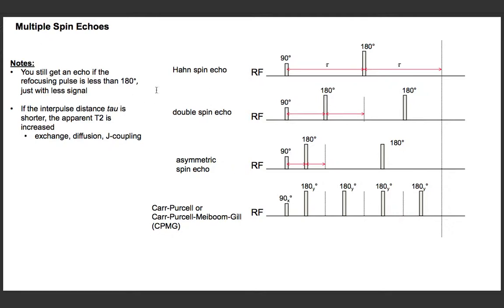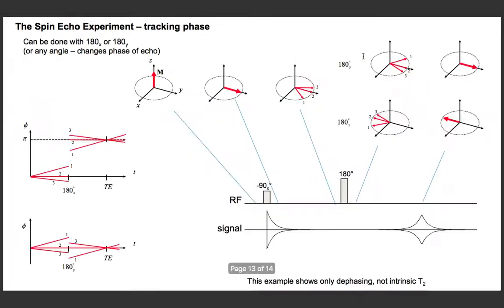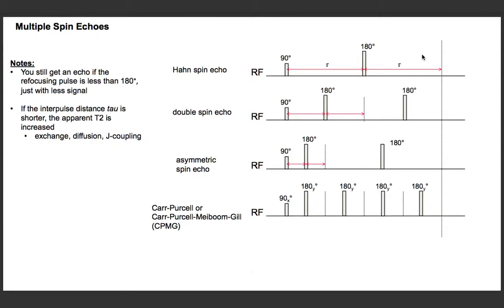Two other points I wanted to make. When we do these spin echo experiments, I'm saying it's got to be a 180-degree pulse. But in fact, if you do something less than 180, and you really can never do a perfect 180 over a uniform part in space, you still get refocusing. In these plots on these previous pages, if you do a 120-degree flip, it's a little harder to see how they refocus, but it does work. And in fact, most spin echo experiments, spin echo imaging on scanners, do use pulses more in the 120 to 140-degree range. You do get less signal. You don't get as much focusing, but it's a trade-off because it's kind of expensive to produce a flip angle that high.